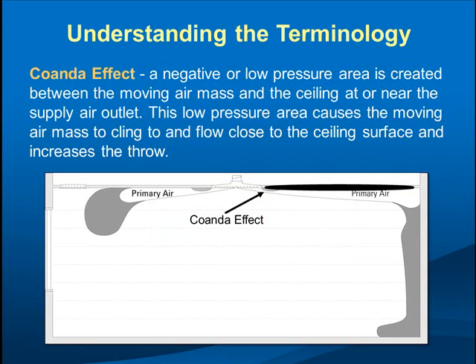The reason we try to make the jet stick to the ceiling is to keep cold air from dumping into the occupied zone where people are sitting. A jet of air has slightly lower static pressure than the surrounding air, so the air around it pushes the jet against the ceiling — we call it Coanda, sometimes Bernoulli. This allows cold air from the diffuser to mix with warm room air and slightly warm up, so it eventually doesn't have enough negative buoyancy to fall into the space and create uncomfortable conditions.